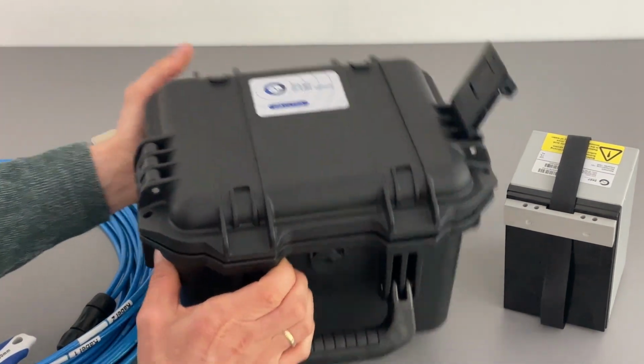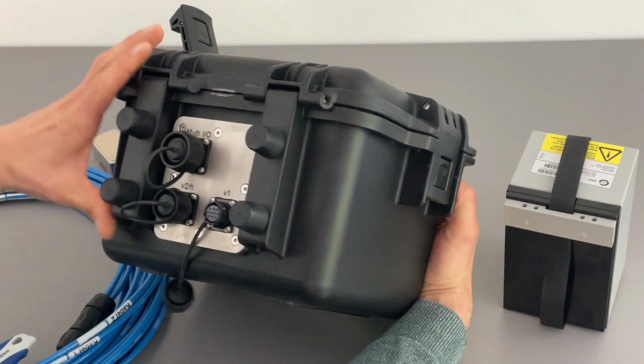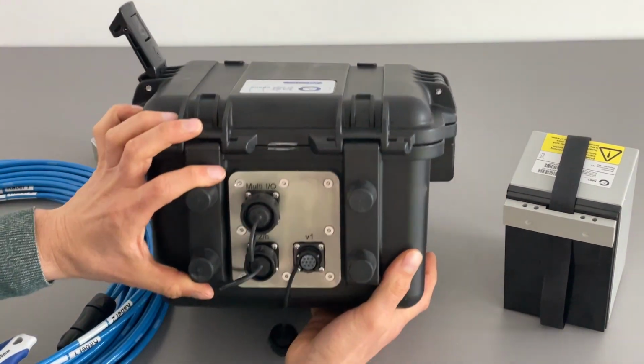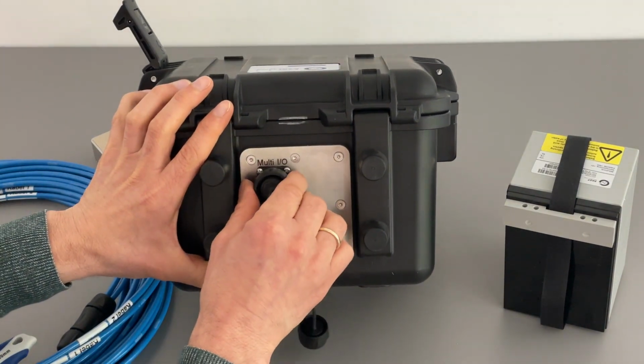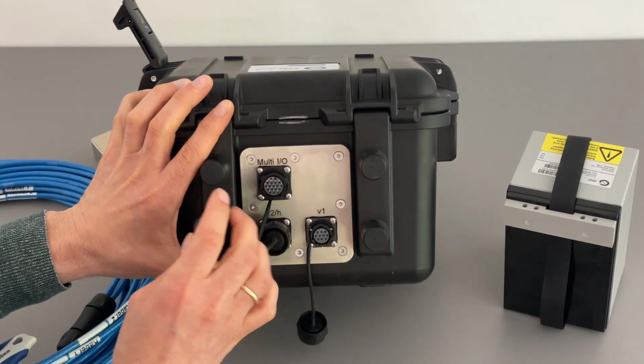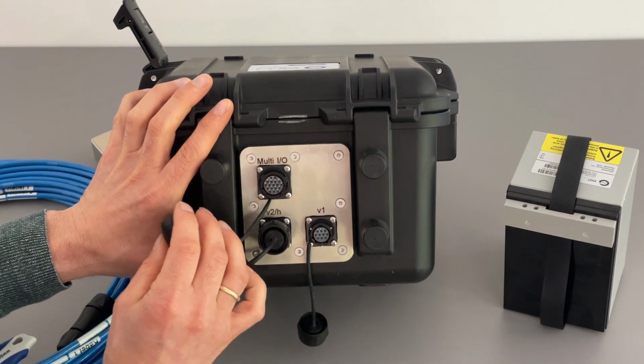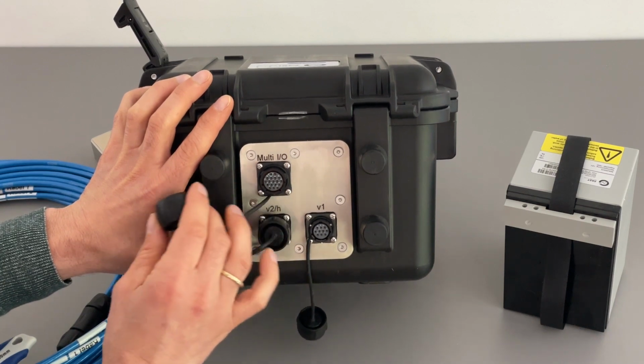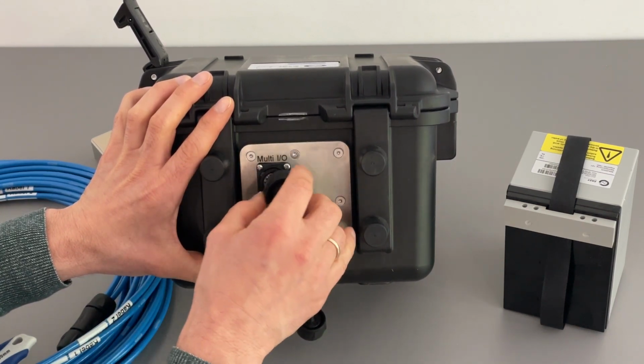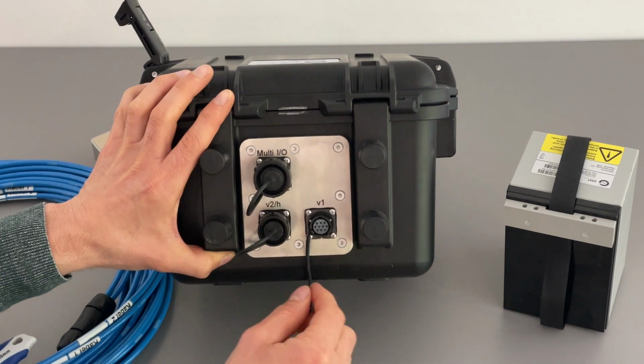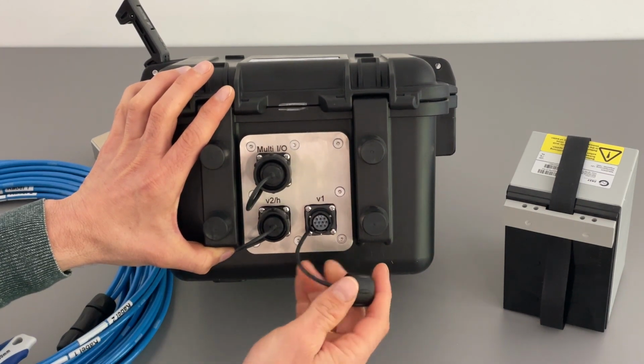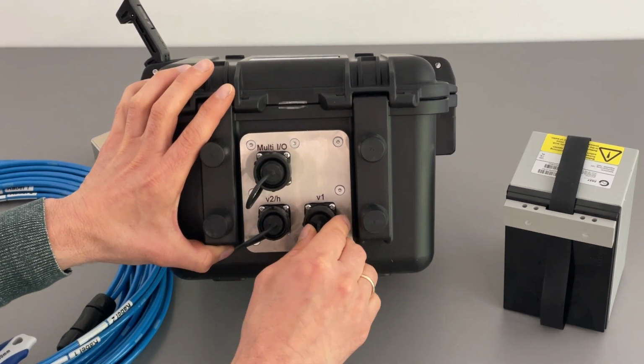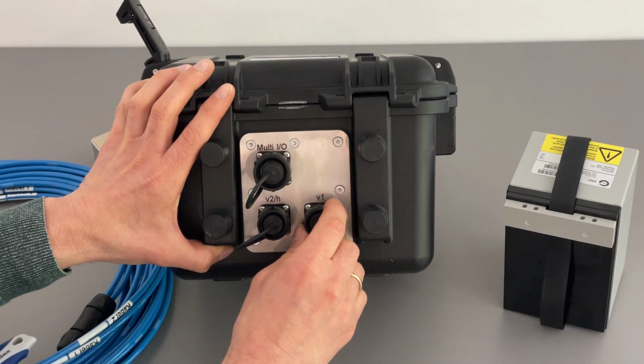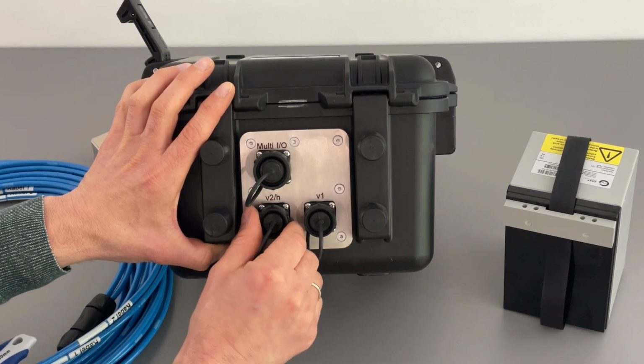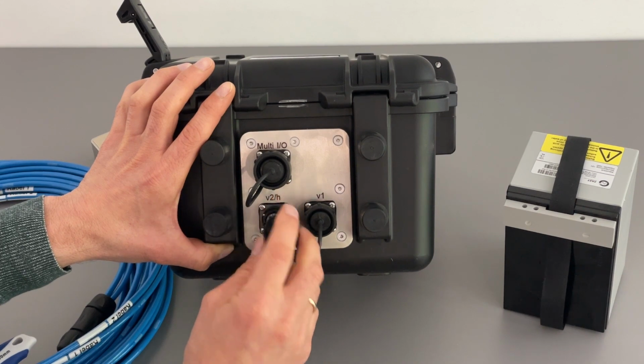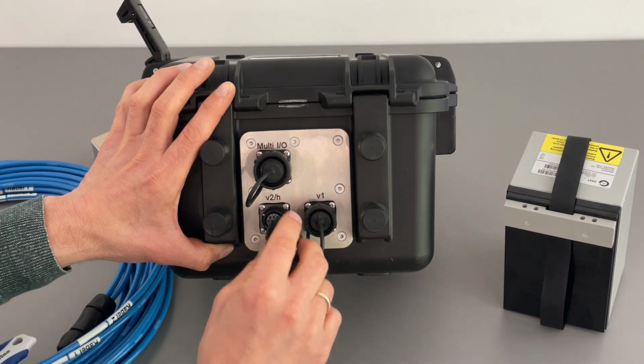On the back of the ZM Ultra we have different sockets for connecting, for example here, an external power source on the multi-IO socket, and or additional external sensors like a pressure sensor, for example. And here on V1 you can connect the standard ultrasonic sensor pair, and on V2 optionally a second ultrasonic sensor pair.